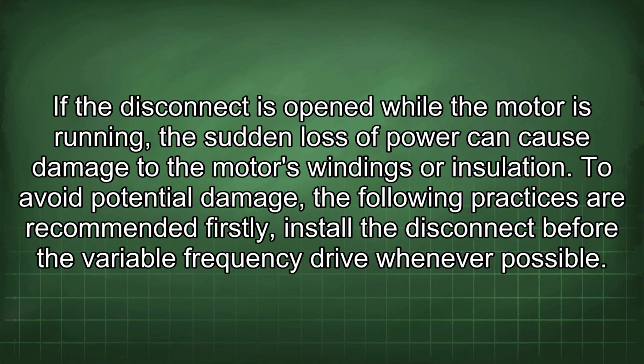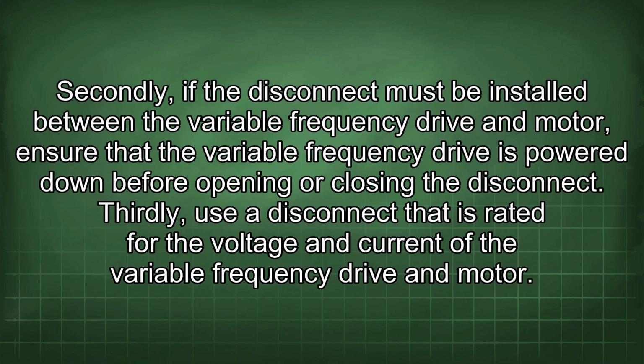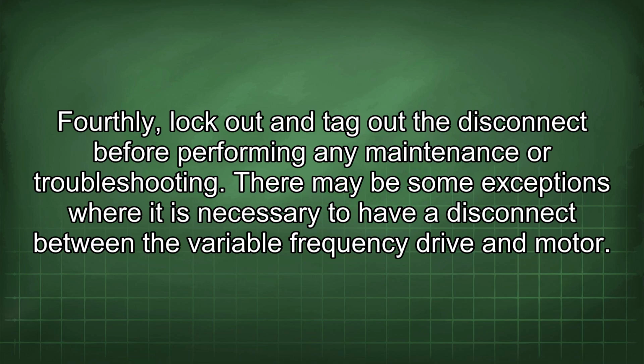If the disconnect is opened while the motor is running, the sudden loss of power can cause damage to the motor's windings or insulation. To avoid potential damage, the following practices are recommended. Firstly, install the disconnect before the variable frequency drive whenever possible. Secondly, if the disconnect must be installed between the variable frequency drive and motor, ensure that the variable frequency drive is powered down before opening or closing the disconnect. Thirdly, use a disconnect that is rated for the voltage and current of the variable frequency drive and motor. Fourthly, lock out and tag out the disconnect before performing any maintenance or troubleshooting.